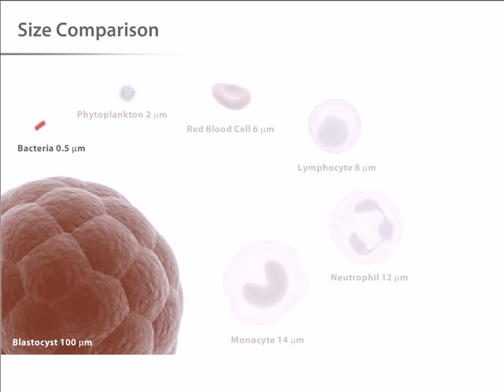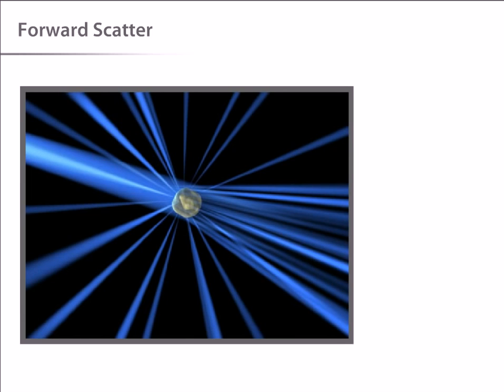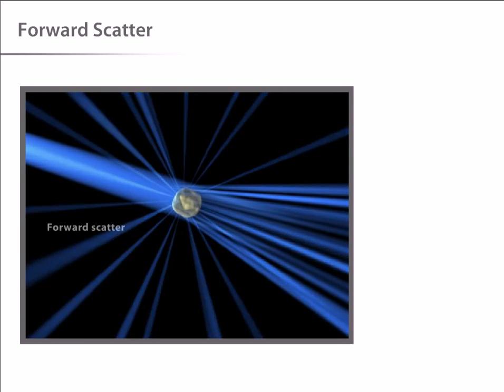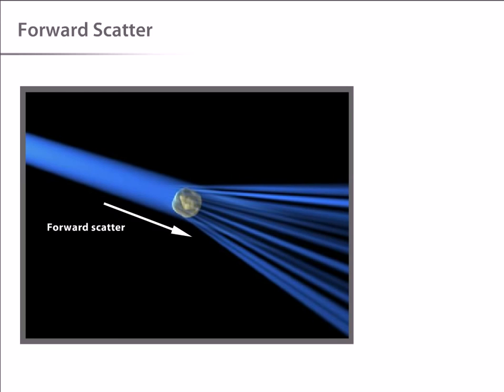Now let's see how laser light is used to detect individual cells in the stream. As a cell passes through the laser, it will refract or scatter light at all angles. Forward scatter or low angle light scatter is the amount of light that's scattered in the forward direction as laser light strikes the cell.